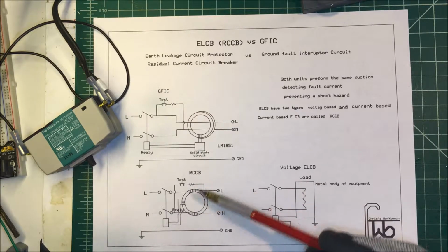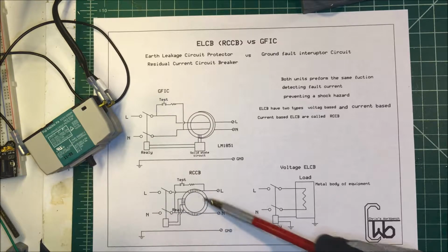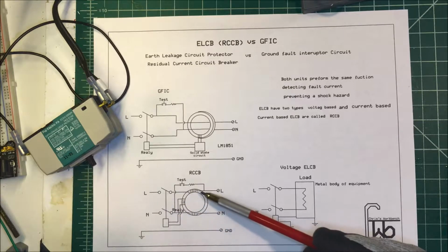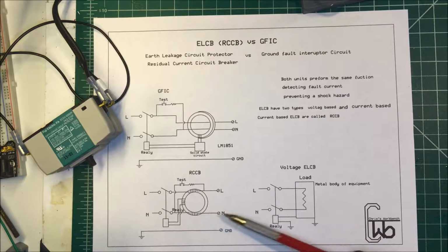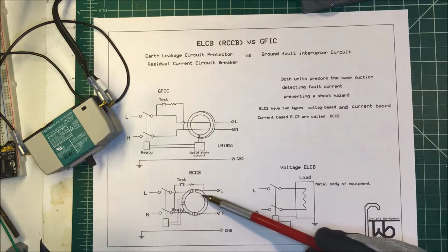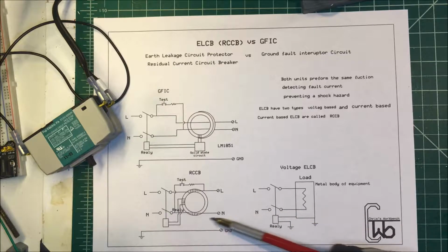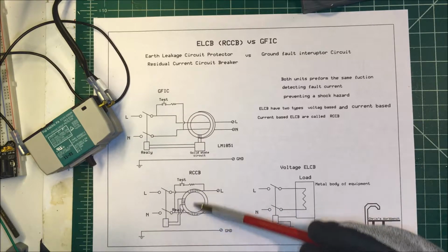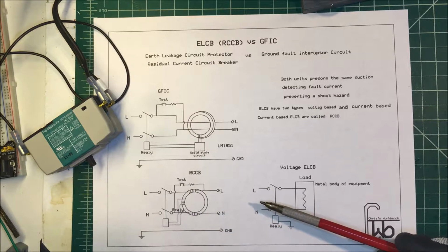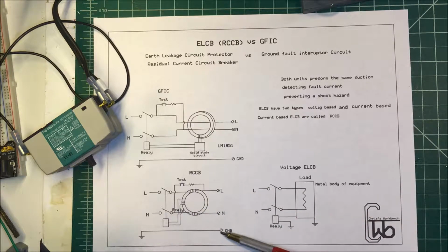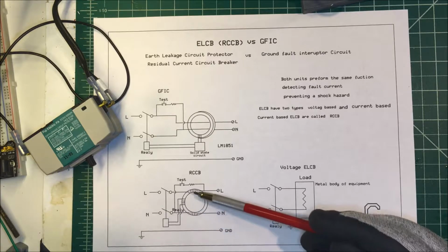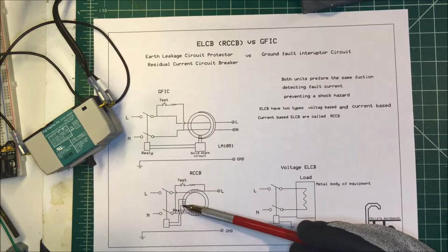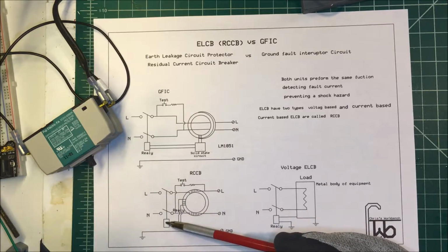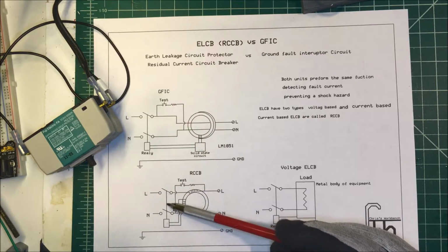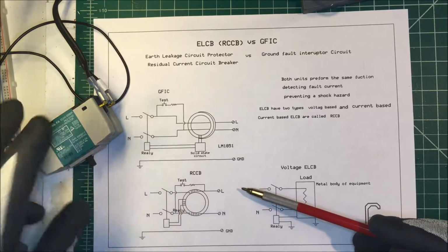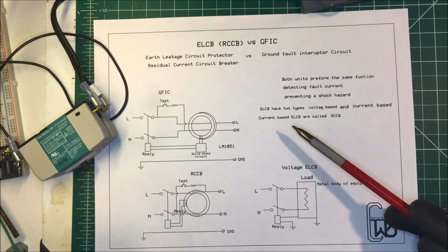This here is an RCCB. It has an iron core in here, and the line comes in and it wraps around the core, and the neutral does the same thing here. If electrons happen to be flowing in this direction and they come back in this direction through the neutral, they'll cancel each other out and there won't be a magnetic field in this core here. If some of the electrons happen to go to ground, then there'll be an unbalance here and it'll produce a magnetic field in the core. It will be picked up by this coil here and trip the circuit breaker, opening it up. That's this one here. We're going to test this one after.